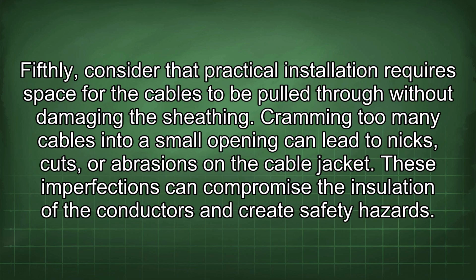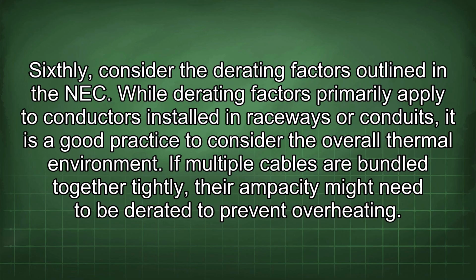Fifthly, consider that practical installation requires space for the cables to be pulled through without damaging the sheathing. Cramming too many cables into a small opening can lead to nicks, cuts, or abrasions in the cable jacket. These imperfections can compromise the insulation of the conductors and create safety hazards. Sixthly, consider the derating factors outlined in the NEC. While derating factors primarily apply to conductors installed in raceways or conduits, it is a good practice to consider the overall thermal environment. If multiple cables are bundled together tightly, their ampacity might need to be derated to prevent overheating.